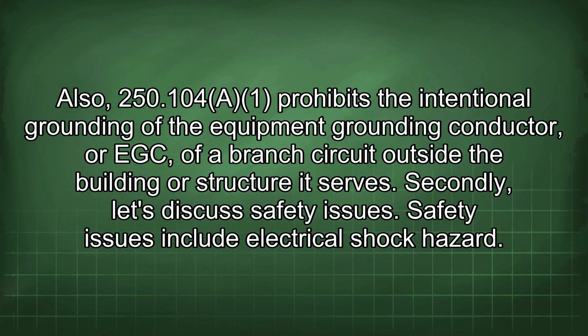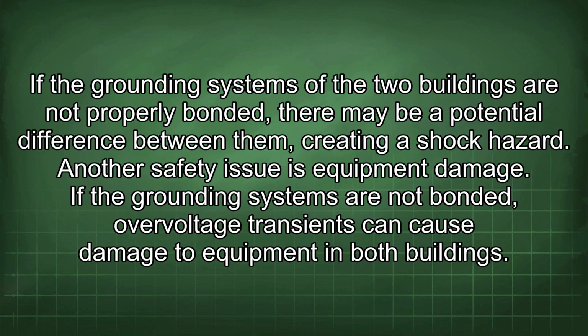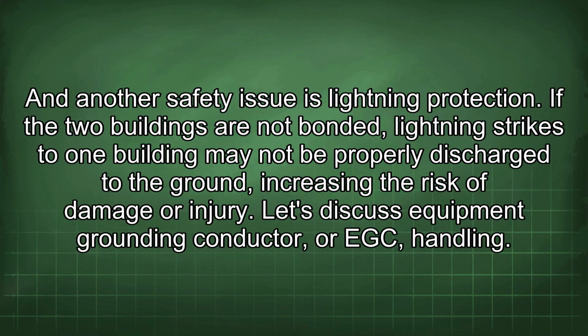Safety issues include electrical shock hazard. If the grounding systems of the two buildings are not properly bonded, there may be a potential difference between them, creating a shock hazard. Another safety issue is equipment damage. If the grounding systems are not bonded, overvoltage transients can cause damage to equipment in both buildings. And another safety issue is lightning protection. If the two buildings are not bonded, lightning strikes to one building may not be properly discharged to the ground, increasing the risk of damage or injury.